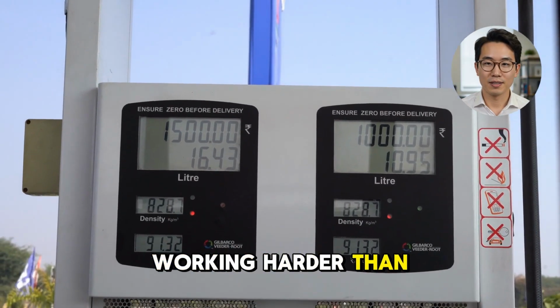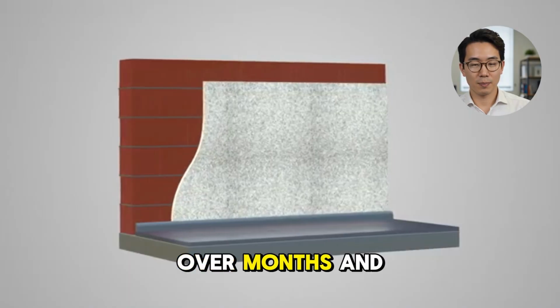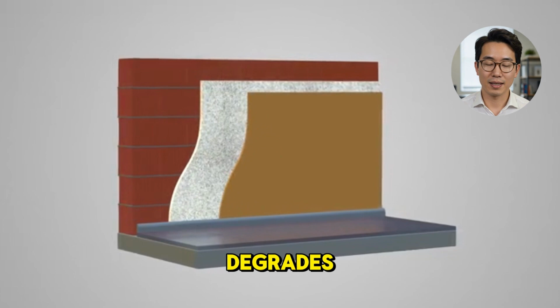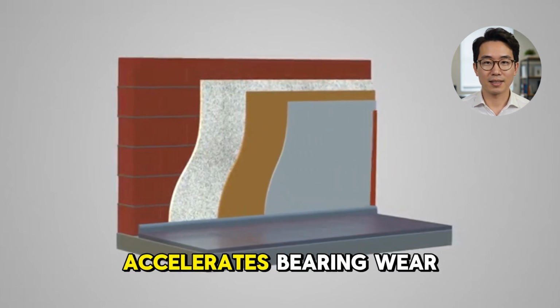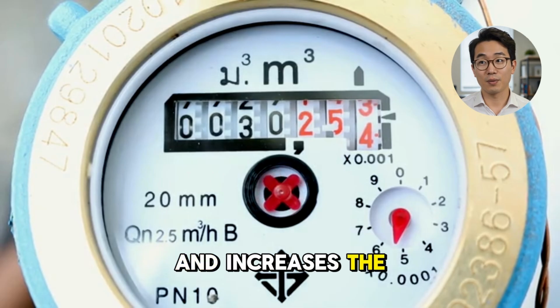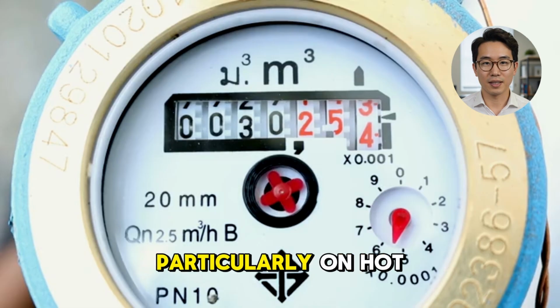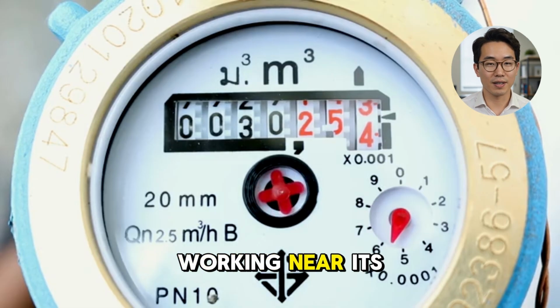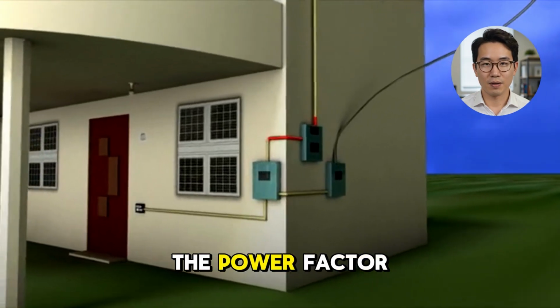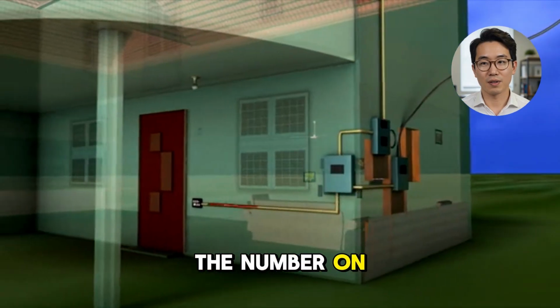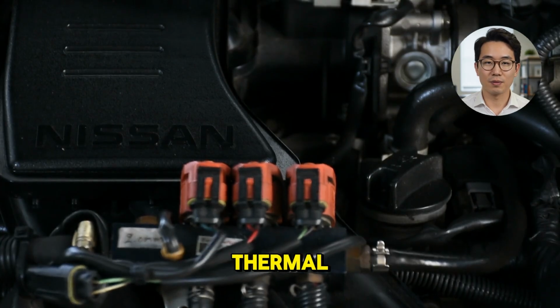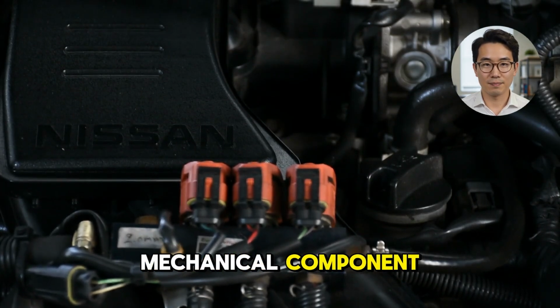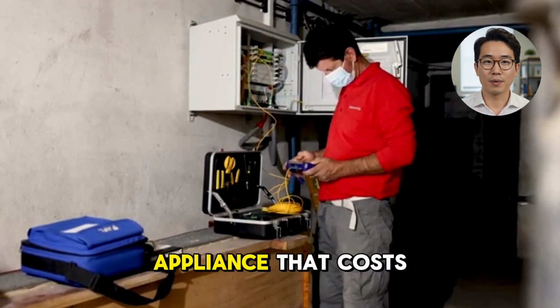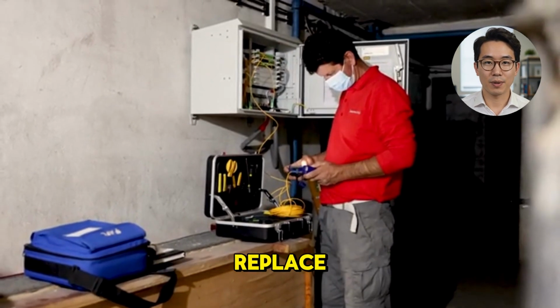The motor is working harder than the actual cooling load requires. Over months and years, that excess heat degrades the insulation on the motor windings, accelerates bearing wear, and increases the likelihood of startup failures, particularly on hot days when the motor is already working near its load limit. When you correct the power factor, you're not just reducing the number on your electricity bill. You're reducing the thermal stress on a major mechanical component. You're potentially extending the life of an appliance that costs thousands of dollars to replace.